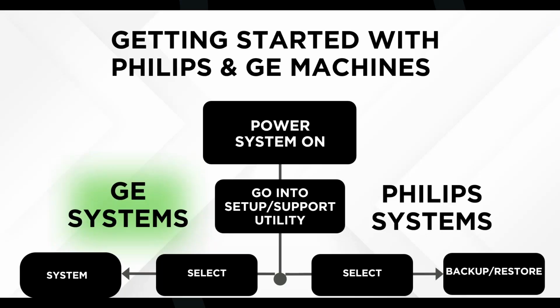So we covered IP address, one of the keys. We covered license options, which is another key. And user-defined settings were all covered in our backup restore. Now, a couple things just to go over on the Philips side of the systems. If the system was up and running, but it was still giving you some type of issues, you can come over here and run a system confidence test. I think it's like an 8 or 9 minute system test. It runs the same diagnostic tests as if you were to log into the system, or Philips was there to look at it.